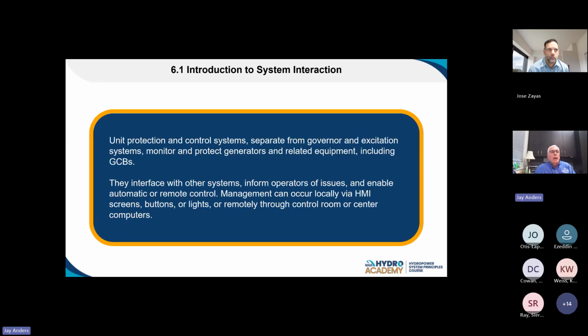Unit protection and controls is sort of separate from the governor excitation system, but it highly ties into those systems. A lot of times these governors are just looking for an input to increase or lower speed. But in and of itself, the governor controls itself and will shut itself down—it has its own protection systems to protect the governor.